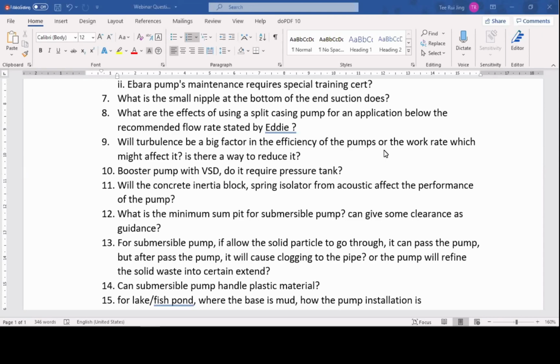With the client, is there a way to reduce it? Yes, definitely. That is to redesign or to change. You cannot do anything to the pump if the turbulence is already caused. Usually the turbulence is not caused by the pump, but by either the pipe or the suction pipe, which could be smaller than the inlet of the pump. Then it's also one issue. So there's nothing that you can do on the pump side. You have to change your suction side of the pump.